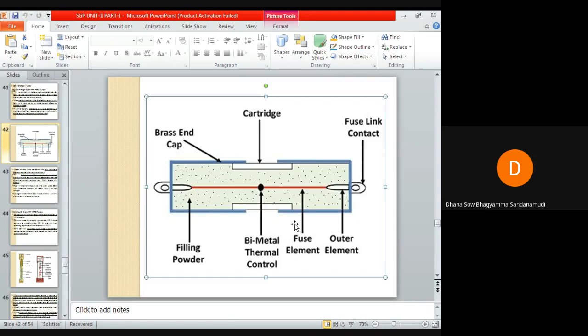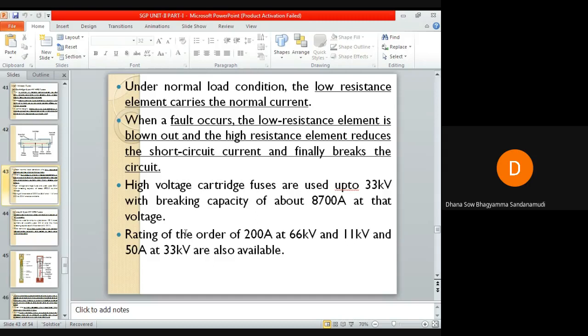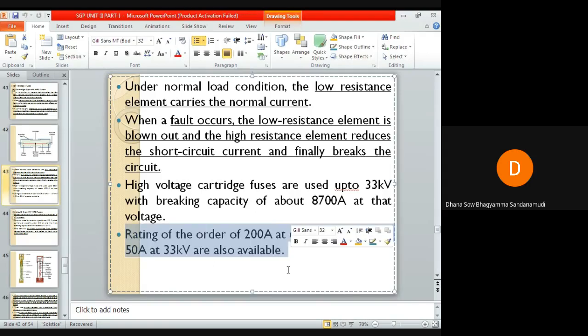The high voltage cartridge fuses are usually used up to 33 kilovolts with a breaking capacity of about 8700 amperes at that voltage. Ratings of the order of 200 amperes at 66 kilovolts and 11 kilovolts, and 50 amperes at 33 kilovolts, are also available. So these are all the ratings of this.